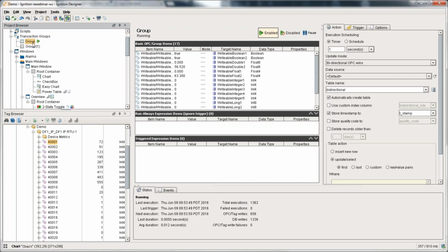So basically, you're putting more control into your hands, versus historian where everything's done for you, because nobody wants to have to worry about that when they're configuring it. The transaction groups don't have any compression. They don't do interpolations. It's a different model. But commonly customers will use a combination of the two to really get a complete system that's there.